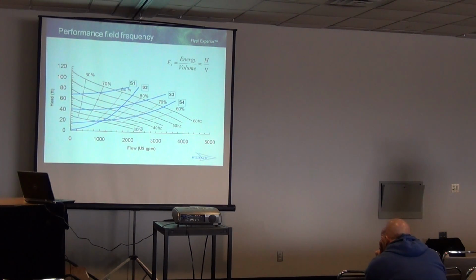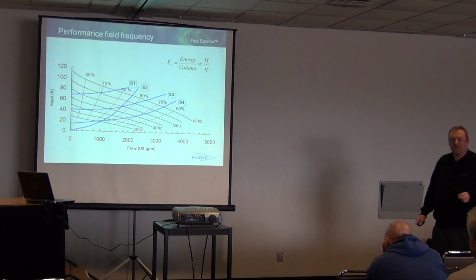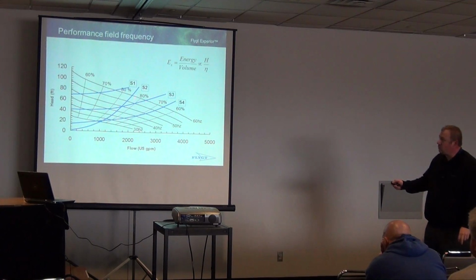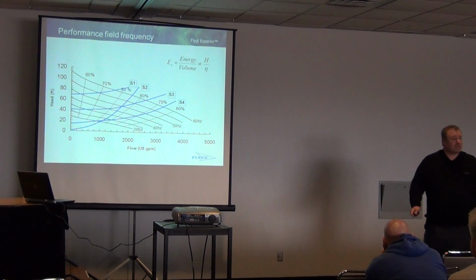So when we do a pump selection for you, optimally what we're trying to do is find a system curve that lays in the best spot it can all the way through that BEP. We're trying to optimize and keep that pump at best efficiency point as much of the runtime as we possibly can. The further you get away from it, we lose efficiency to the right, and the further we get away over here on the left, we're working our way away. So that's the key to all this: maximizing the efficiency of your pump selection and keeping it in what we call the sweet spot of that pump for the longest period possible.